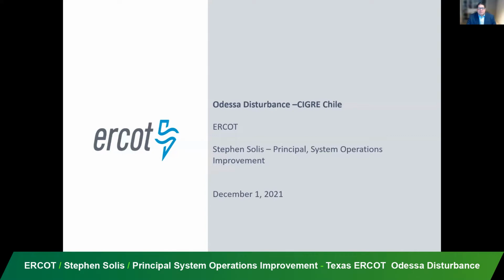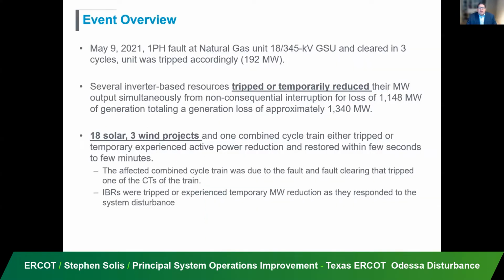I'm going to be speaking with you today about a disturbance that occurred on the system on May 9, 2021, that we refer to as the Odessa disturbance, just because of its general location. When we look at this particular event, it was a single phase to ground fault on the lightning arrestor right outside of a natural gas unit. It was a normally clearing fault, 3 cycles. So as expected, the unit tripped off. But what was unexpected is the amount of other resources that reacted negatively to that event.